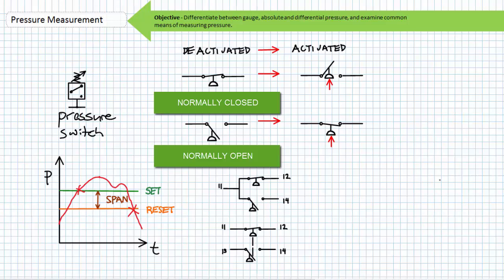The electrical schematic symbol includes a semicircle with a flattened bottom, which gives a clue as to how a pressure switch operates. Fluid under pressure is exposed to a distendable or movable disk. As pressure distorts the disk, electrical contacts change states when a certain level of distortion is achieved. As previously stated, pressure switches exposed to pressures in excess of manufacturer recommended maximum conditions might be permanently damaged and the switch might activate at incorrect pressures, if it activates at all.